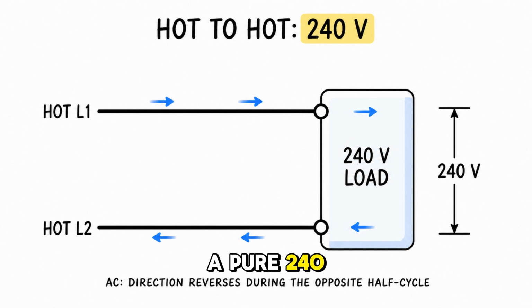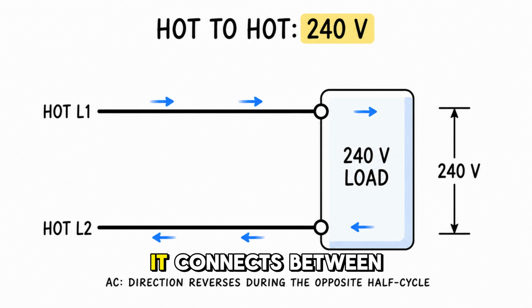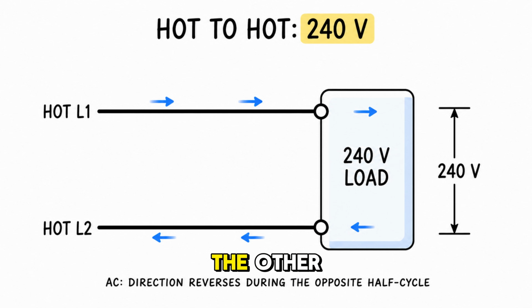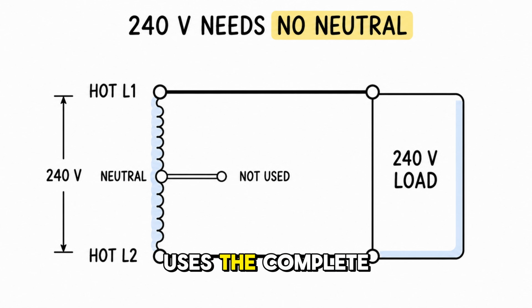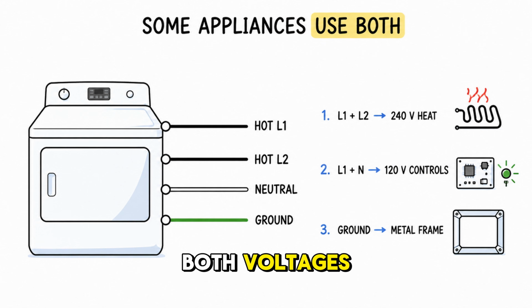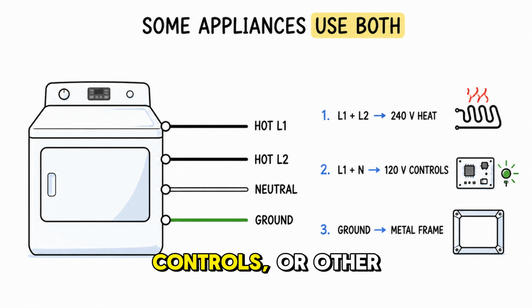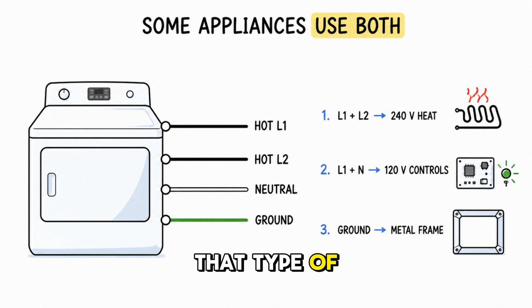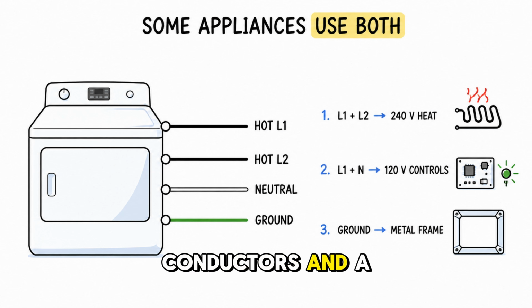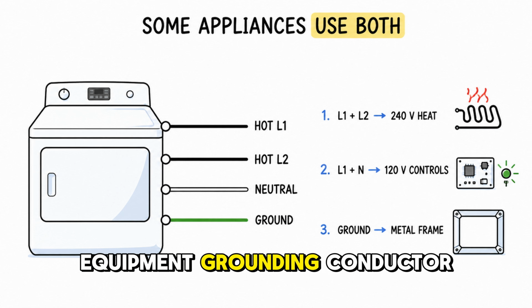A pure 240-volt appliance uses a different path. It connects between the two hot conductors, so current passes through one hot conductor, travels through the load, and continues through the other. Because the appliance uses the complete transformer winding, it does not need a neutral for its 240-volt function. Some appliances need both voltages. A range or dryer may use 240 volts for heating elements while using 120 volts for lights, controls, or other components. That type of appliance receives both hot conductors and a neutral, along with the equipment grounding conductor.